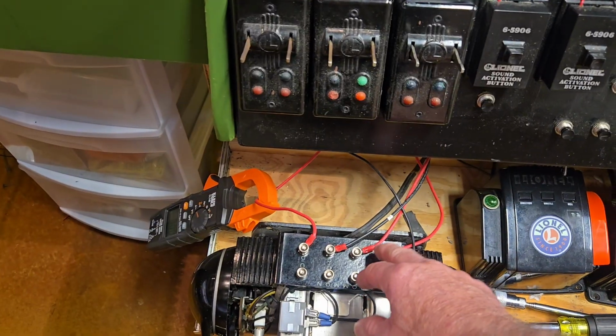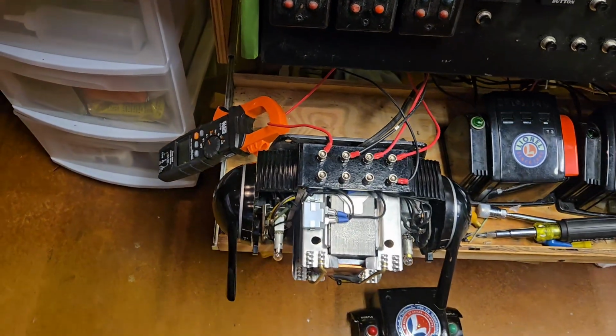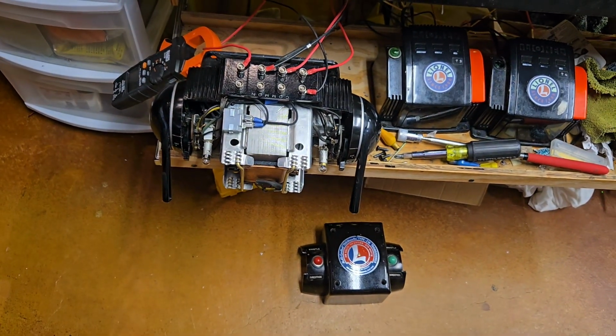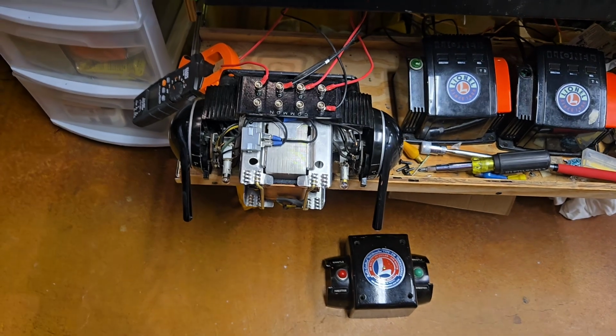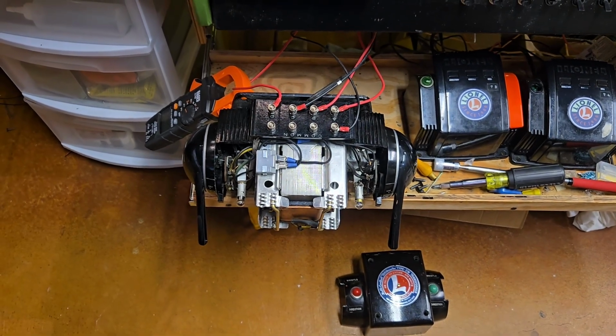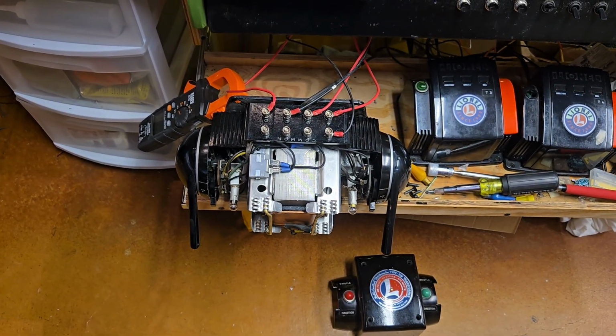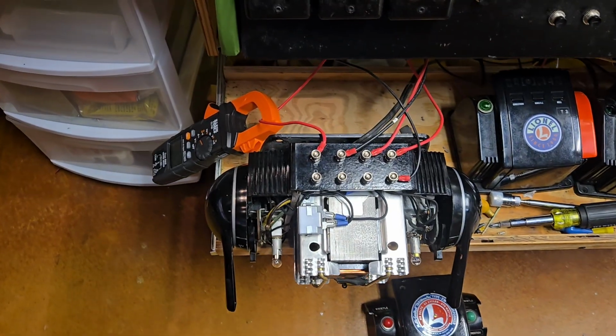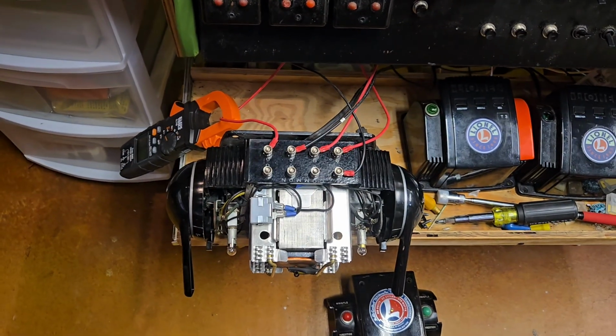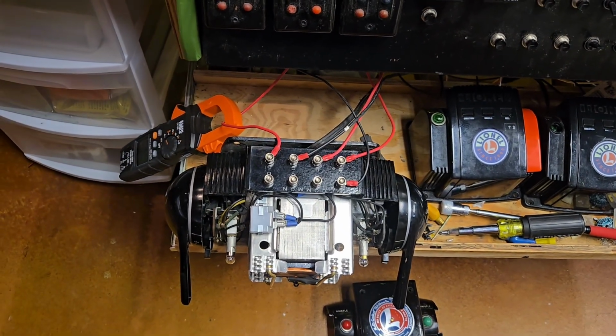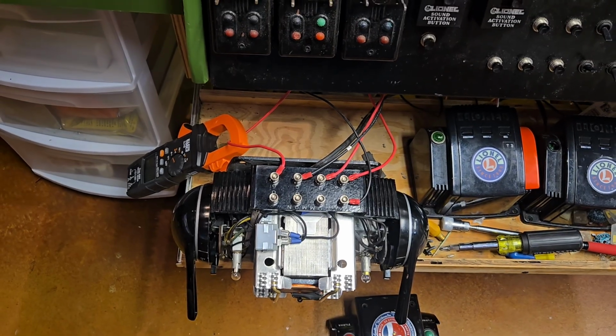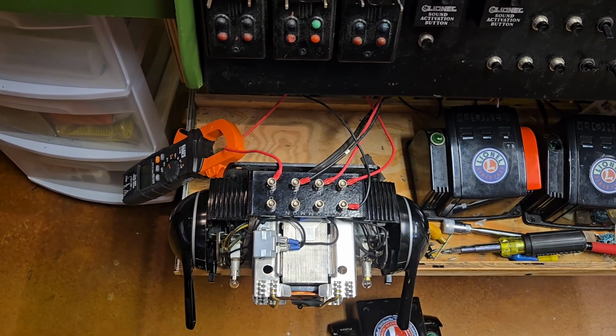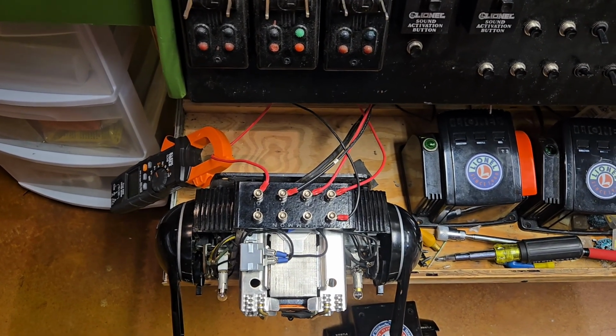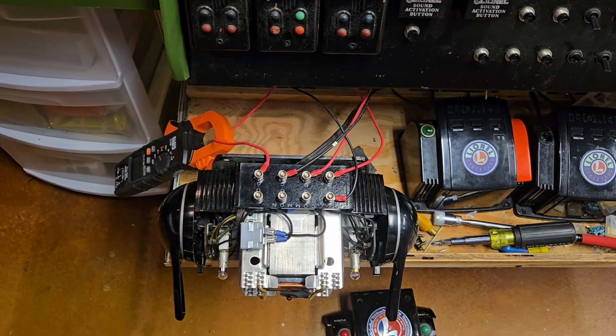So I would highly recommend, if you've got a ZW like this with multiple zones, you want to look into not only surge but also protection. When you're putting the TVS surge protector on, just so you know, you're not really doing that for overload. The minute it's put in, it's doing a job—it isn't just waiting for a short to occur. It's not really designed for that.